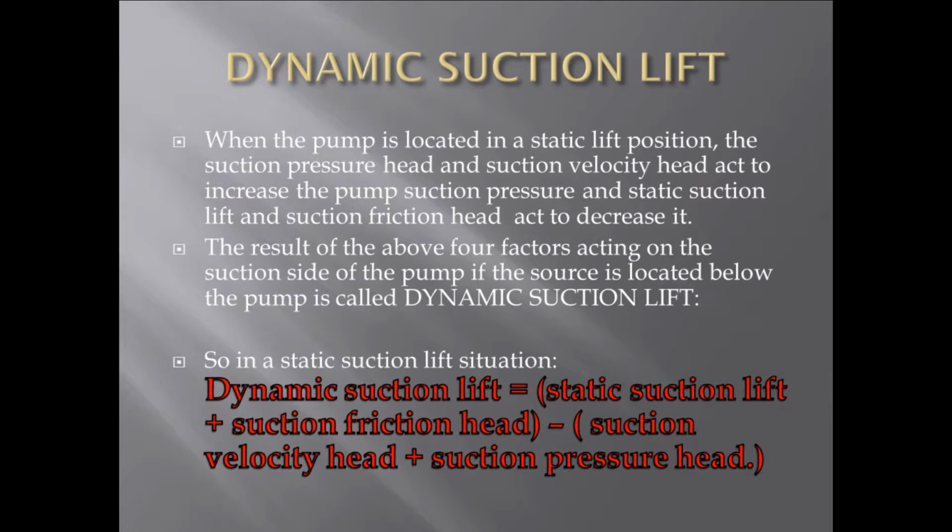When the pump is located in a static lift position, the suction pressure head and suction velocity head act to increase the pump suction pressure, and static suction lift and suction friction head act to decrease it.